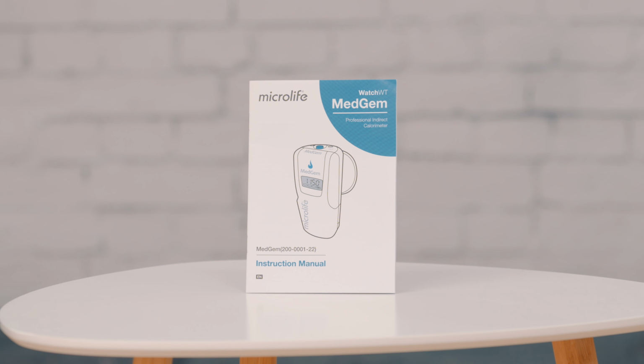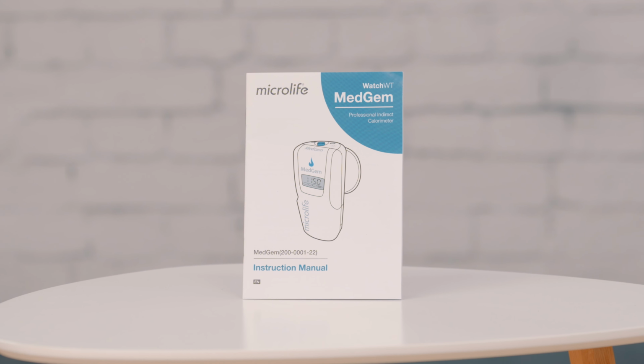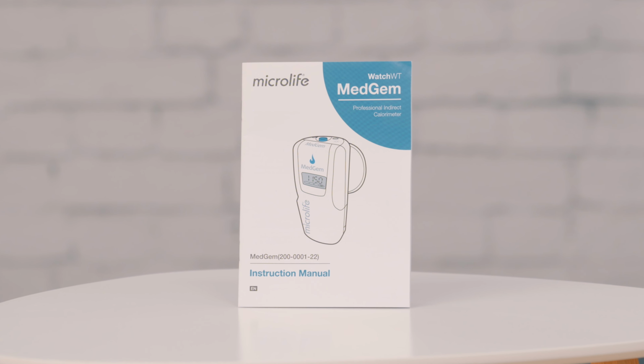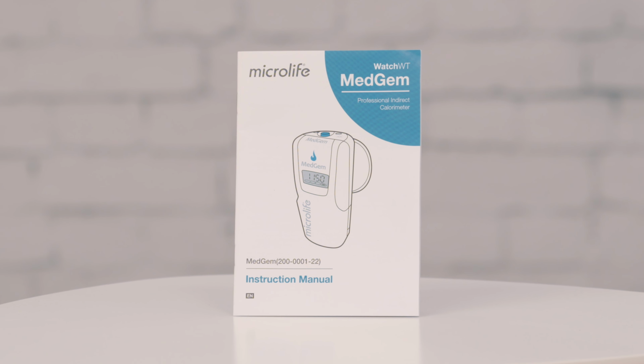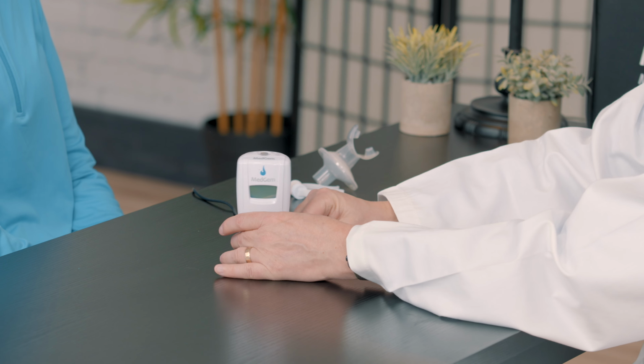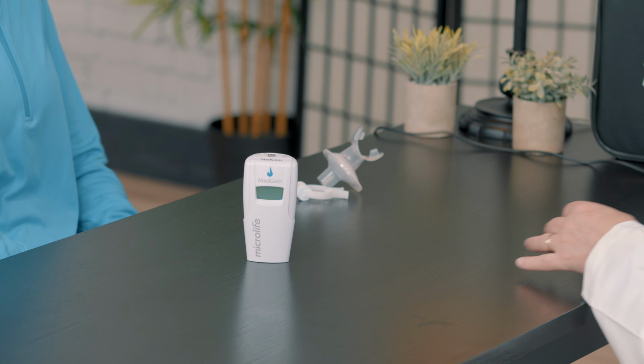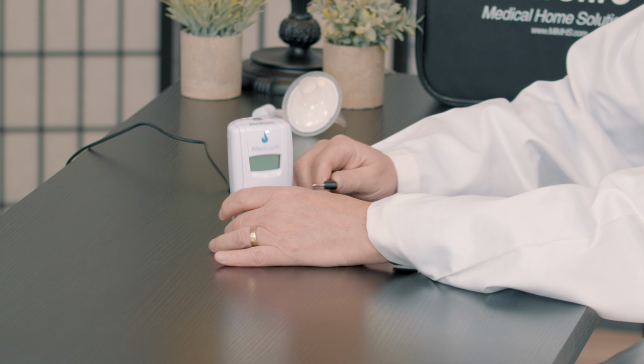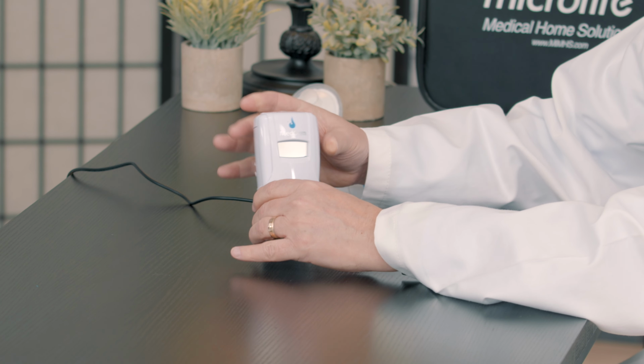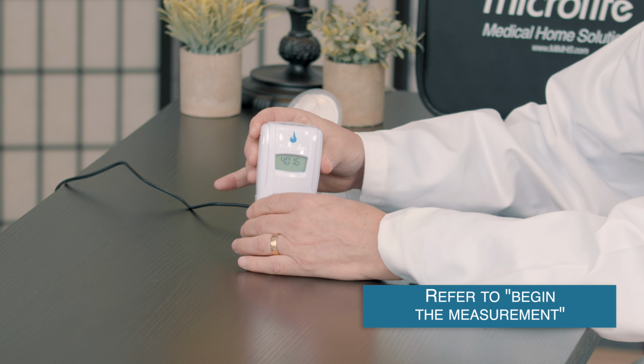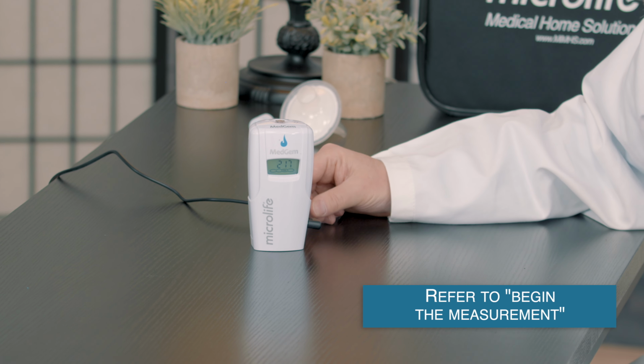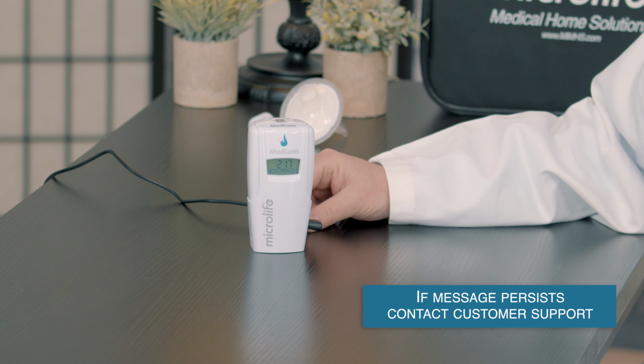Then, use the error code and solution table to remedy the problem in the user manual. Once the problem has been identified, unplug the MedGem device from the power supply to erase the error code. Reconnect the power supply to turn the MedGem device on, and begin the measurement to restart. If an error message persists, contact your customer support team.